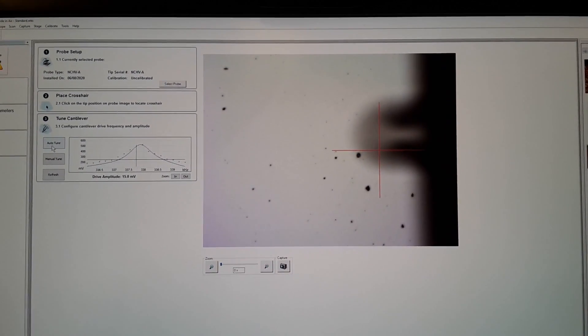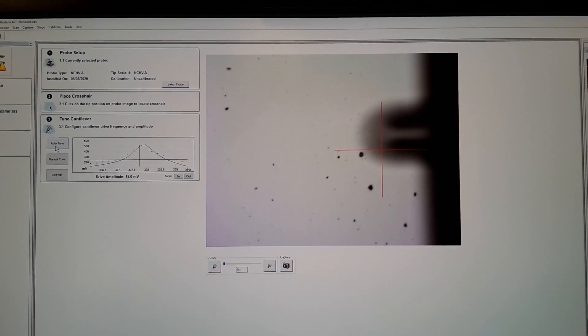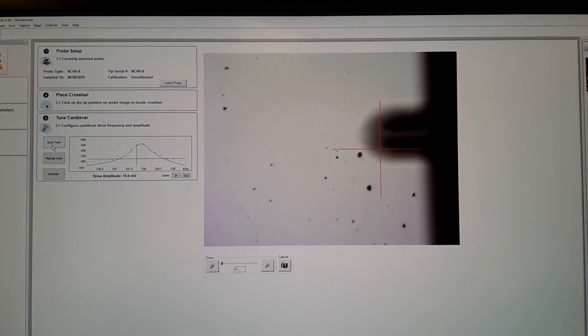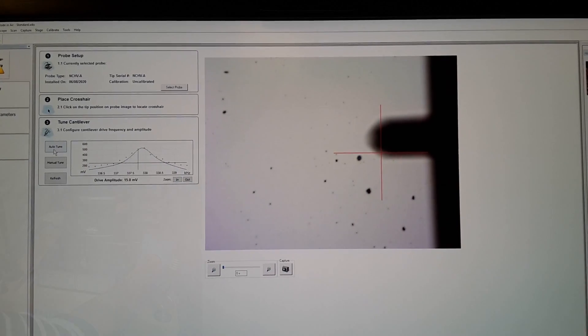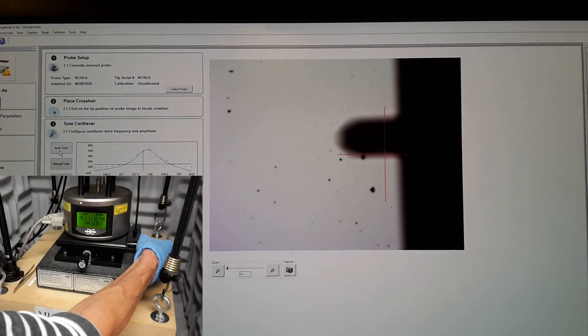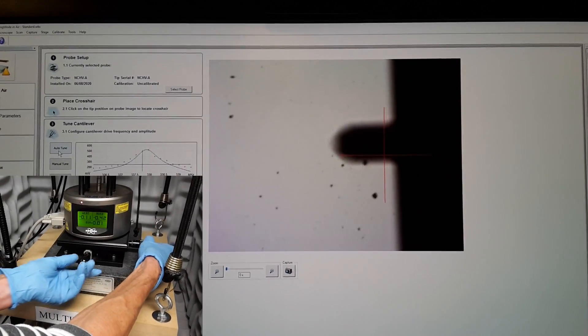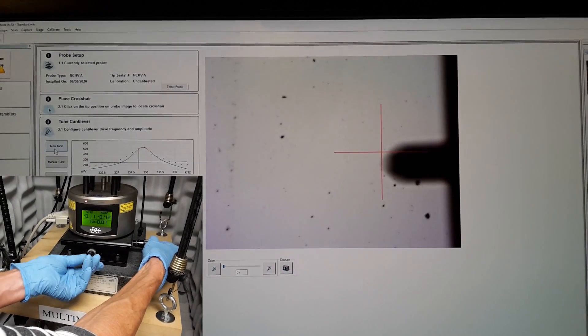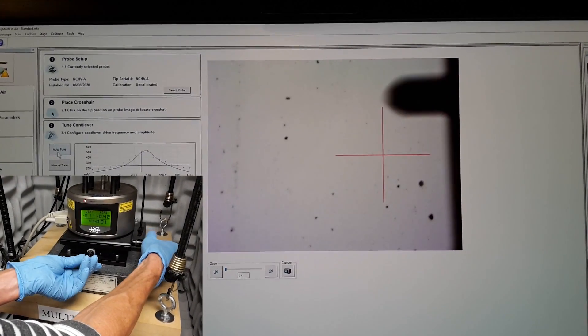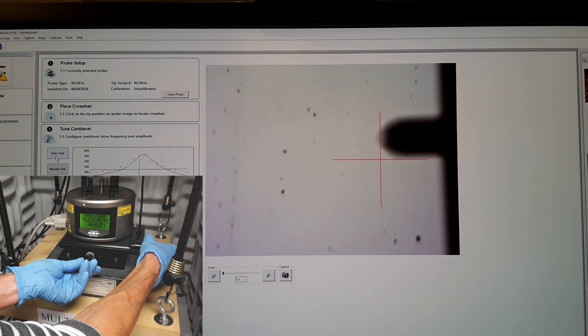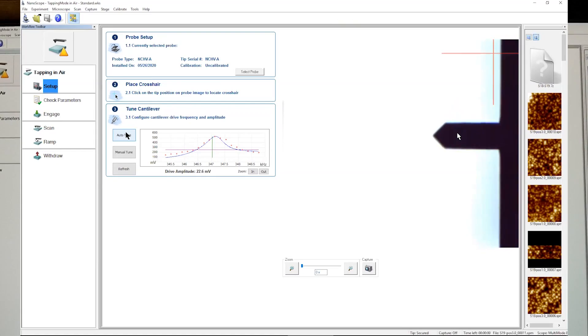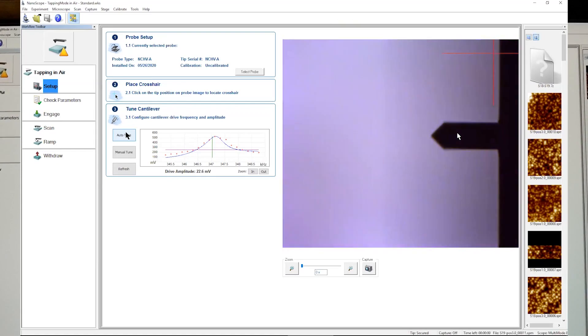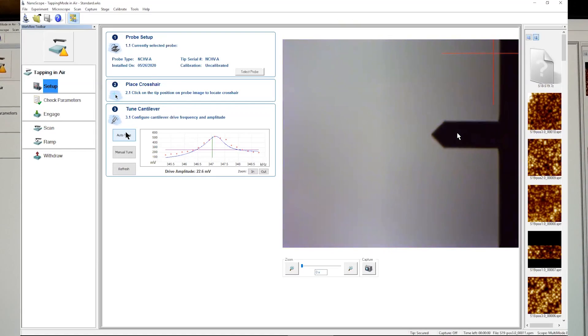It should appear black either completely covering or to the right side of the live camera image. Use the black microscope positioning knobs on the stage to send the probe into the field of view. Then continue to lower the camera to focus on the sample surface.